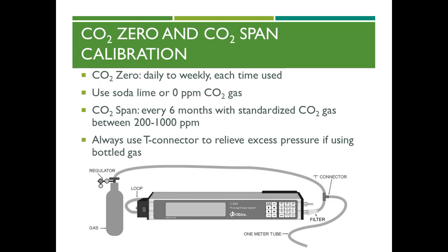Making sure the CI-340 CO2 IRGA is zero calibrated will ensure accurate results and is recommended before each use. To zero calibrate the CO2 sensor, fresh soda lime or 0 ppm CO2 gas, such as dry nitrogen gas, should be used. Soda lime is provided with the instrument for the CO2 zero calibration process. As always, allow the 0 ppm CO2 gas to run for at least 5 minutes before determining if zero calibration is necessary.